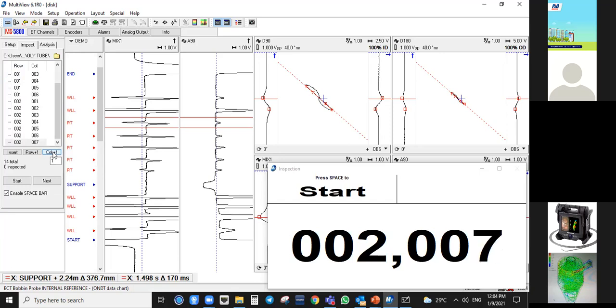6, 7. Okay, and then you just continue depending on the number of rows and columns that you have. Okay, so this is quite important when you are using Multi-View as the software that you need to put on your list. You must make sure that the numbers tally with the number of tubes that you're inspecting. Okay, this is quite different when you're using Carto or Tube Pro.